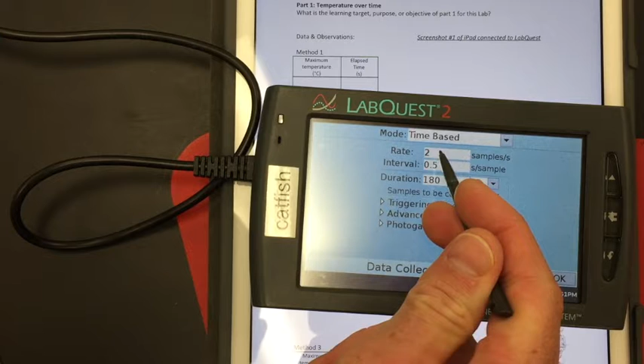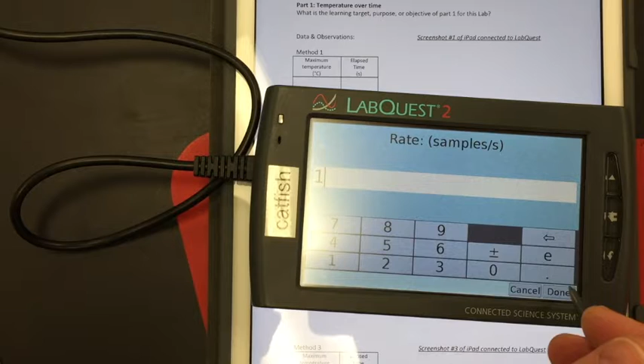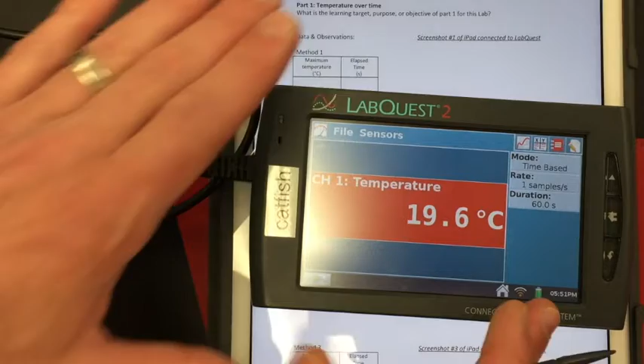We're going to leave it time-based, and change the rate to maybe 1 sample per second, so every second it'll take a reading. We're going to run this for 1 minute, but I'll leave it in seconds, so we know 1 minute is 60 seconds. So that's what that'll look like. Hit OK, and now the device is ready to collect data.